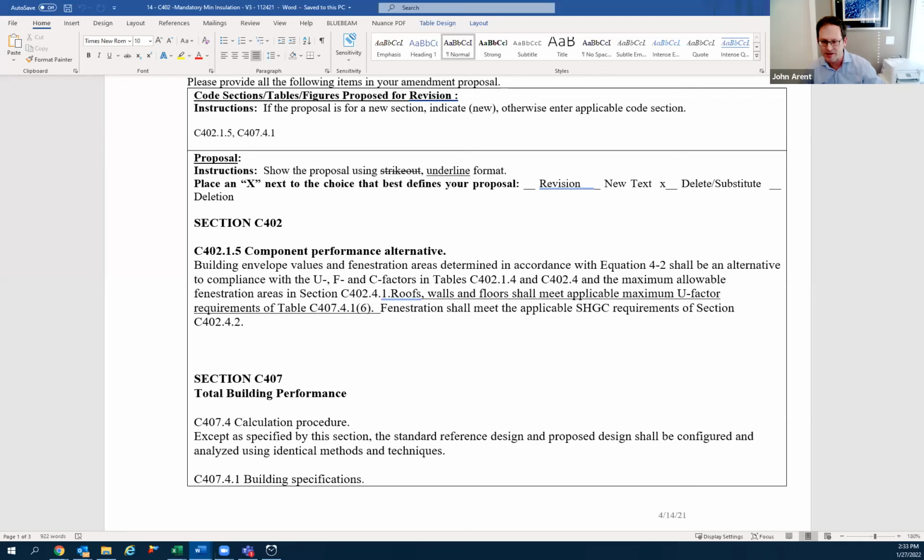That doesn't actually impact stringency directly, but what it does do is set a base minimum or floor that all buildings must achieve. So it limits the amount of trade-offs. And by doing so, it would avoid situations where you have a building that complies with a performance approach, but has a substandard envelope that is very difficult to retrofit in the future. So this is an unusual one because it's deemed a new construction measure, but it really affects the building performance over the building's life.